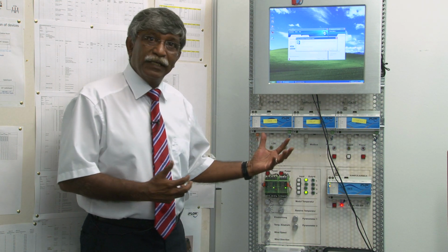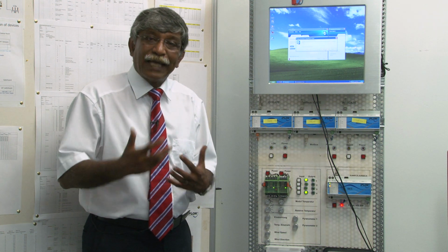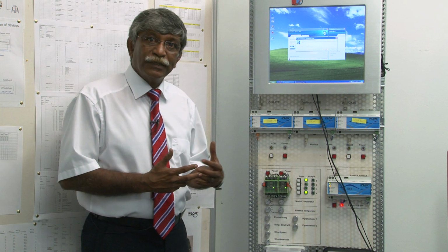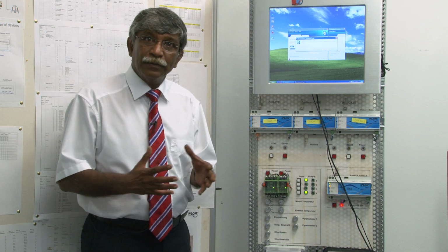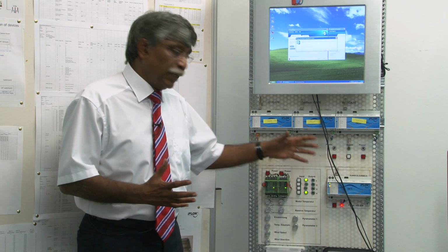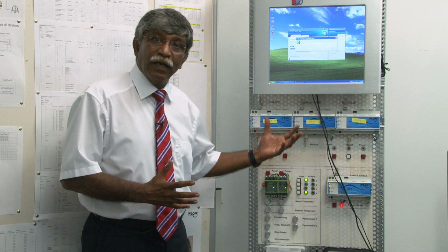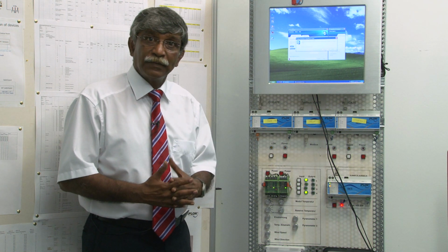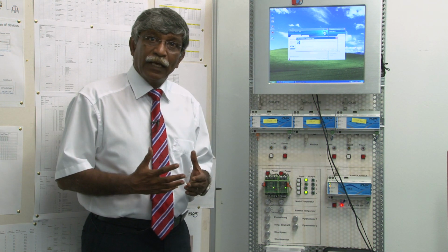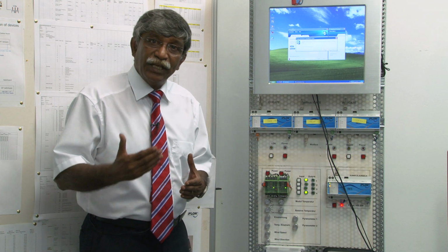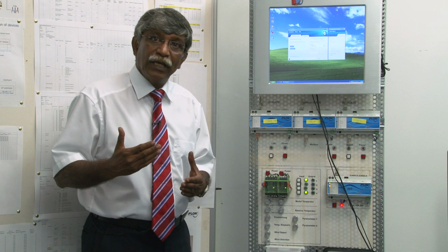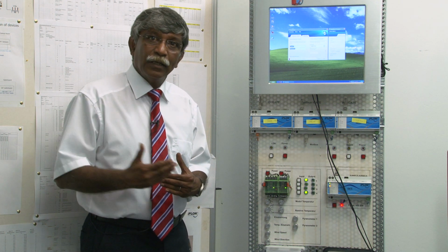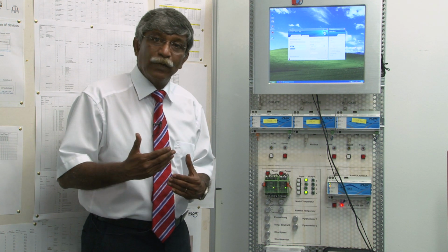So we have the possibility that if a customer tells us what happened on the field, we try to simulate the same scenario here in the simulator and see if the same problem occurred which the monitoring system has given us information about. This way we can at a later stage try to define the scenario under which some malconditions happened, to be able to diagnose exactly where the problem came from.